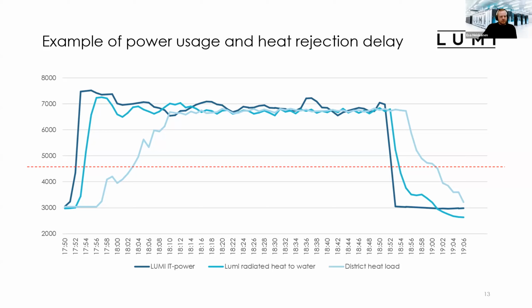It takes a couple of minutes that it starts to radiate from the Lumi secondary cooling loop to our primary cooling loop, and it takes little time when it hits the heat pumps. We have quite a big volume in our cooling loop, so it takes a couple of minutes, up to 4 minutes before it hits the heat pump. And as you can see from this line, the heat pump starts ramping up the power pretty slowly, so it takes over 10 minutes that they are reaching the operational power. But when the power is reached, the production is pretty stable.